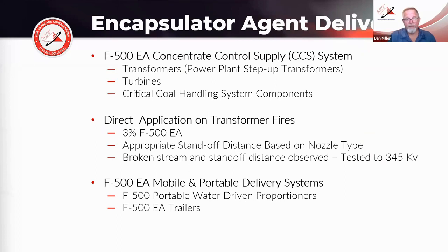So let's talk a little bit about F500, what we call concentrate control supply systems, or our proportioning systems that help proportion F500 into sprinkler systems. They are very applicable to transformers, turbines, critical coal handling system components, and we've designed and supplied components for each, as well as we do on-site commissioning and startup for those. We have direct application on transformer fires at 3% because it is a petrochemical fire with the oil involved.